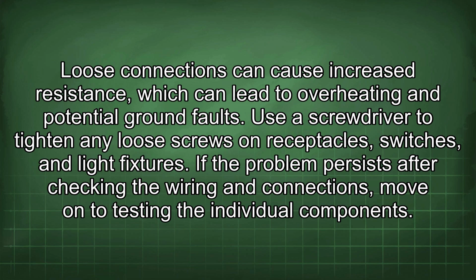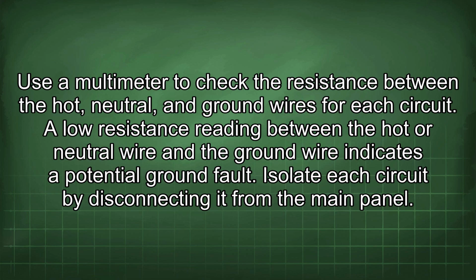If the problem persists after checking the wiring and connections, move on to testing the individual components. Use a multimeter to check the resistance between the hot, neutral, and ground wires for each circuit. A low resistance reading between the hot or neutral wire and the ground wire indicates a potential ground fault. Isolate each circuit by disconnecting it from the main panel.